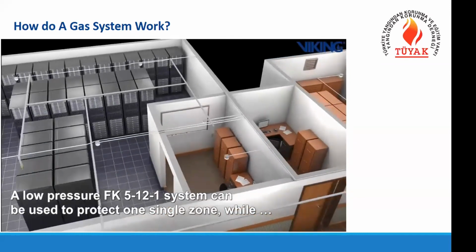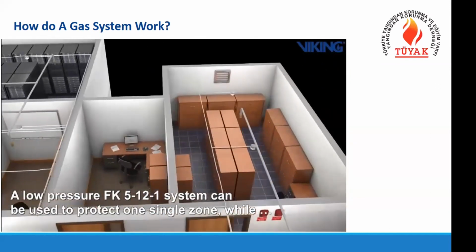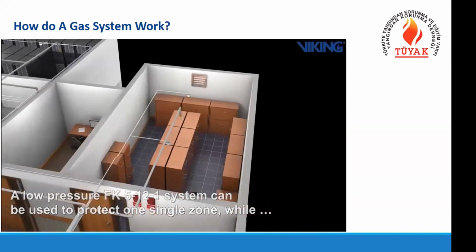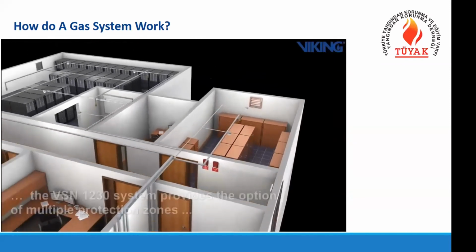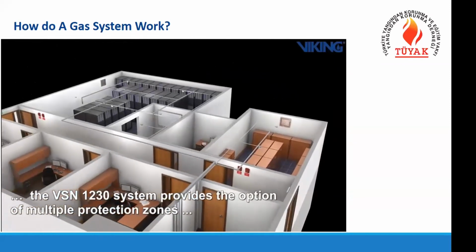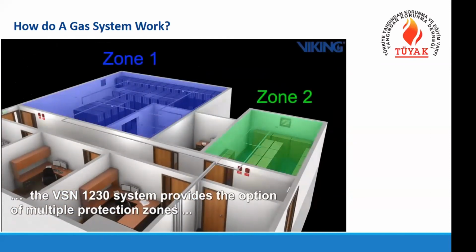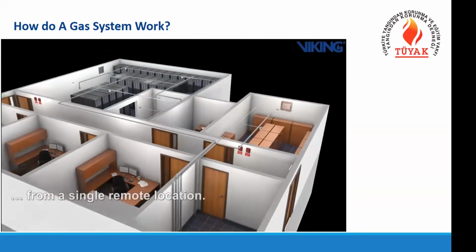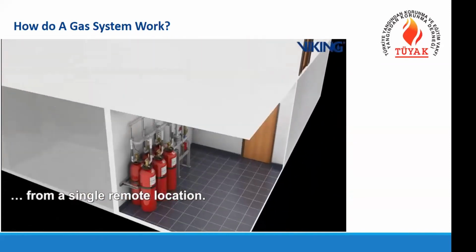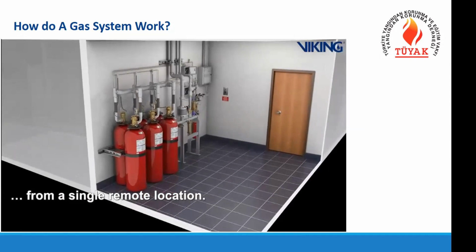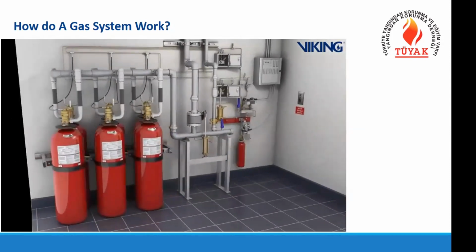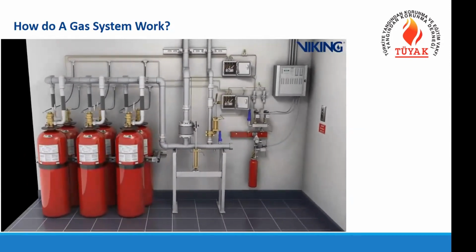This is a chemical gas system for protection of, for example, 2 rooms. One is a server room that has a lot of valuable devices, very expensive devices, and the data stored inside them, very important, and we cannot use water in that room. And the other, zone 2, is the archive room, with very important papers, and also here we cannot use our water systems, in order not to damage important papers.